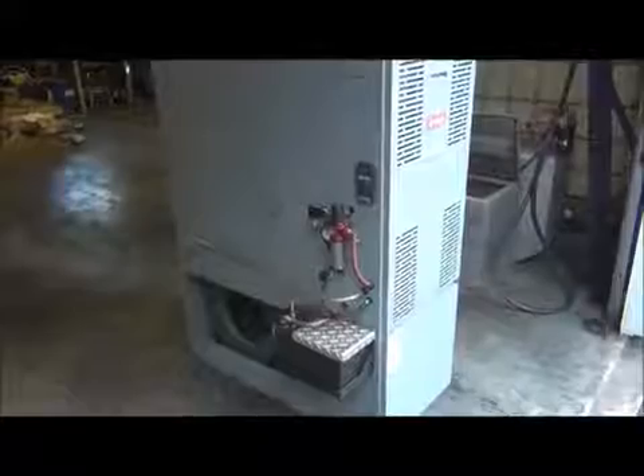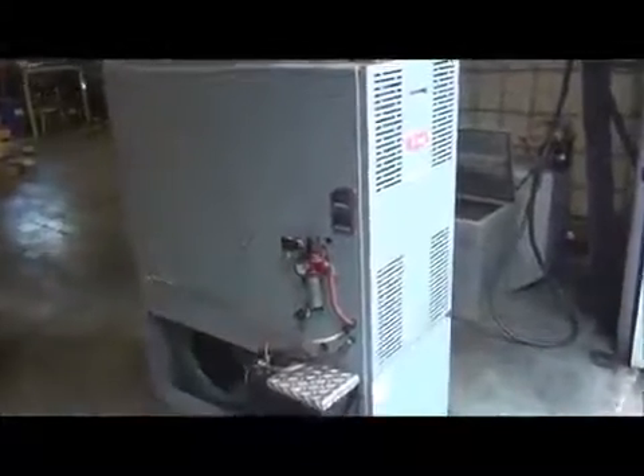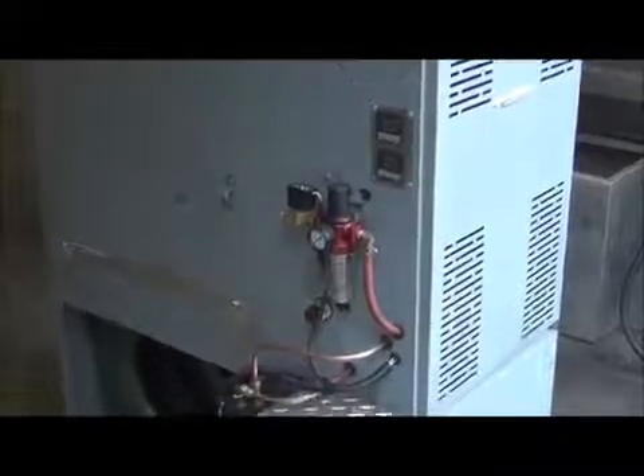Just a quick tour around the furnace here. On the outside of the furnace, we have our two temperature controllers right here. And what these do is they control the temperature of the oil at the nozzle and also the temperature of the oil in the holding tank. We have our air pressure regulator and solenoid valve out here. And what this does is it takes air pressure at whatever your shop air is and reduces it down to about 10 to 20 psi. That's the air pressure we use actually at the nozzle.